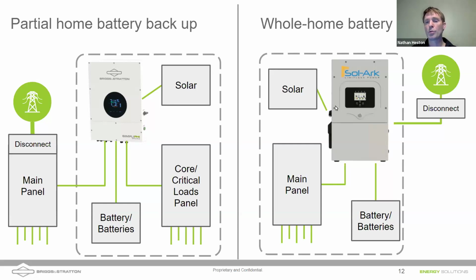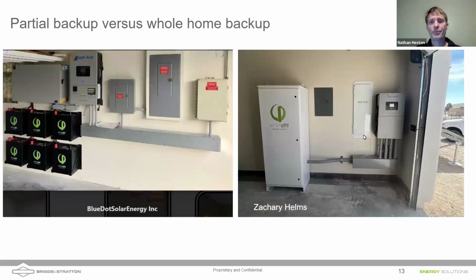If we couple solar in, and solar is in excess, we can get solar to be charging batteries. You can couple in up to, I think it's 38.2 kilowatts on a single Sol-Ark 15k if you use both AC and DC coupled solar. With solar and batteries, you can get 15 kilowatts of load support. So you're really backing up the whole home with the Sol-Ark.